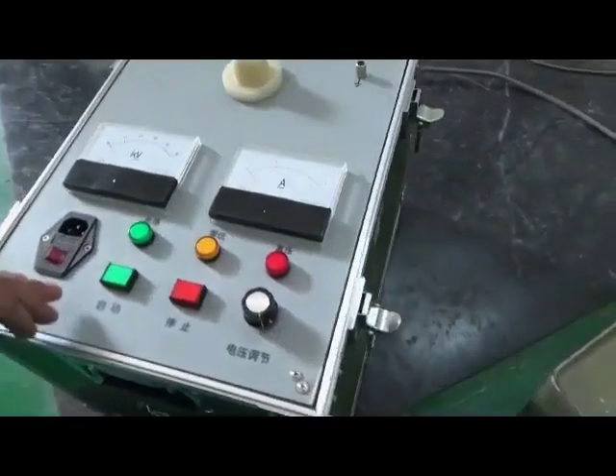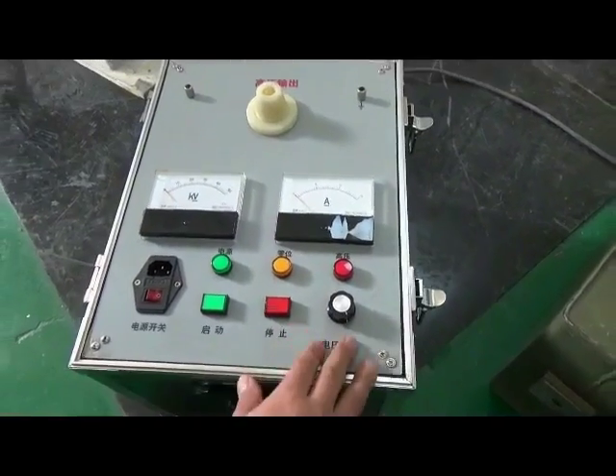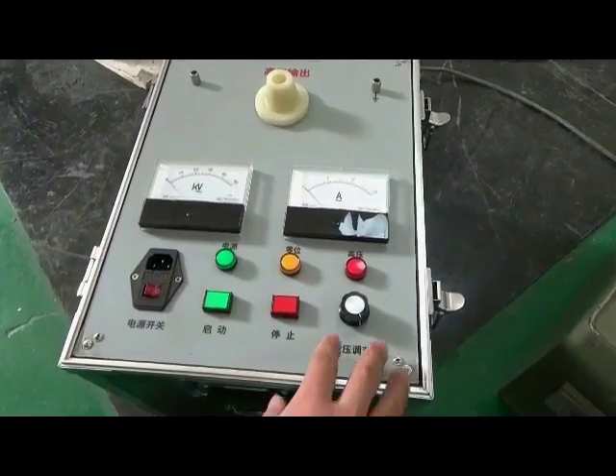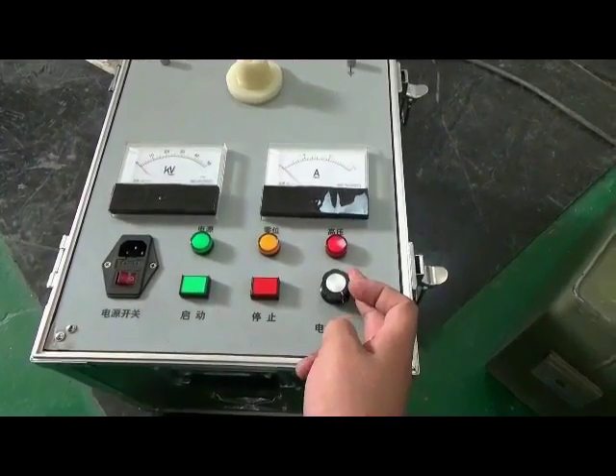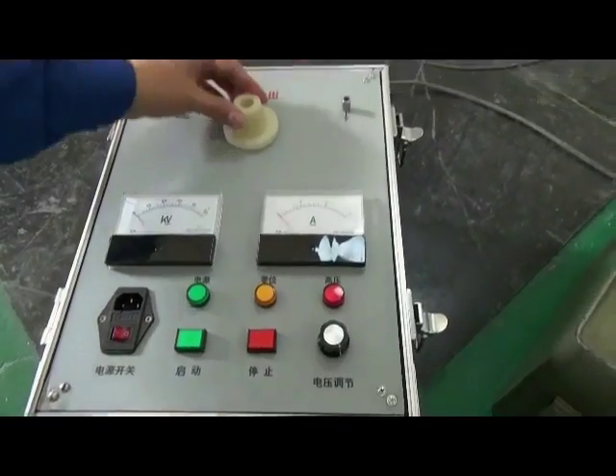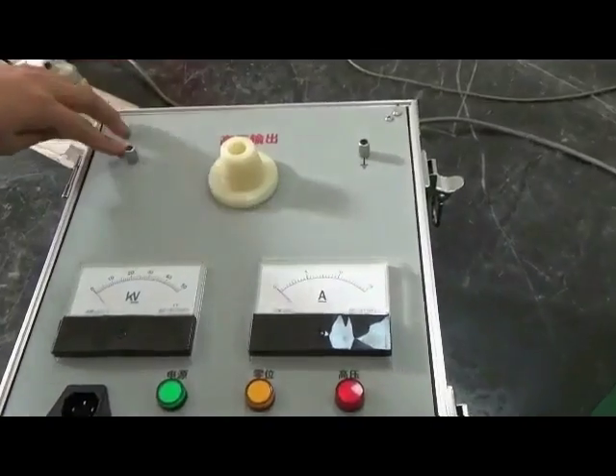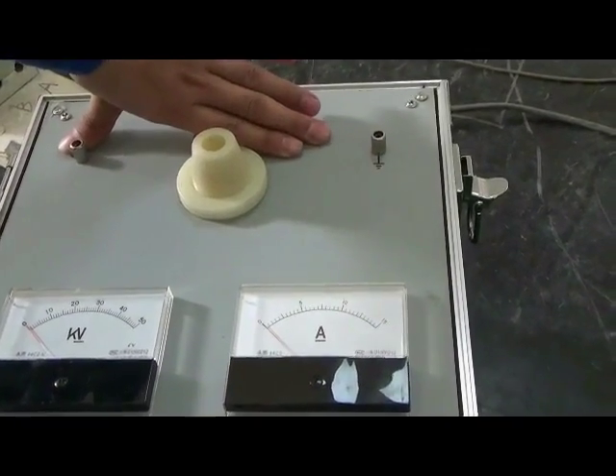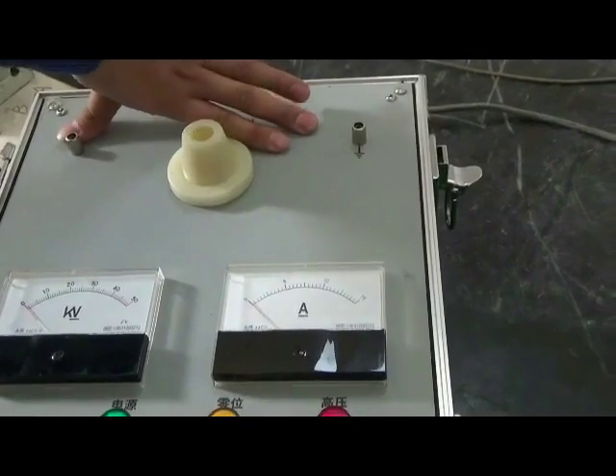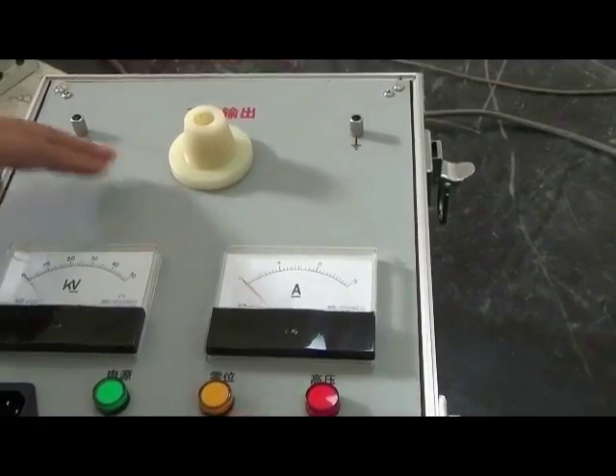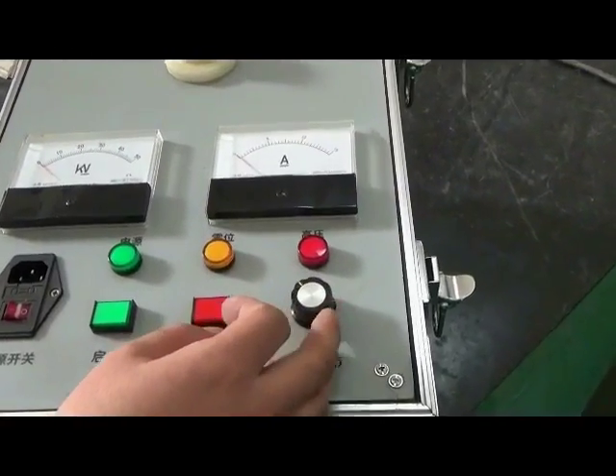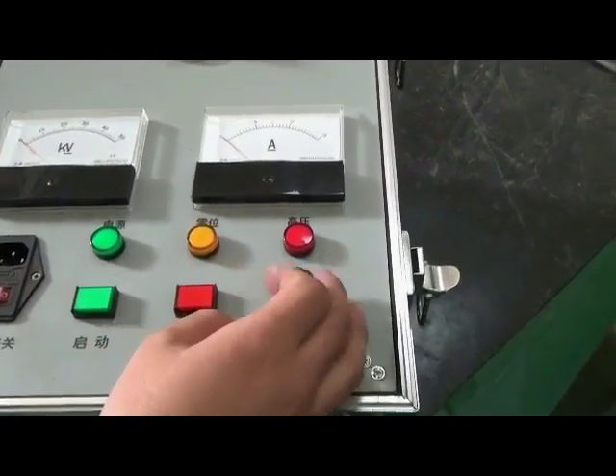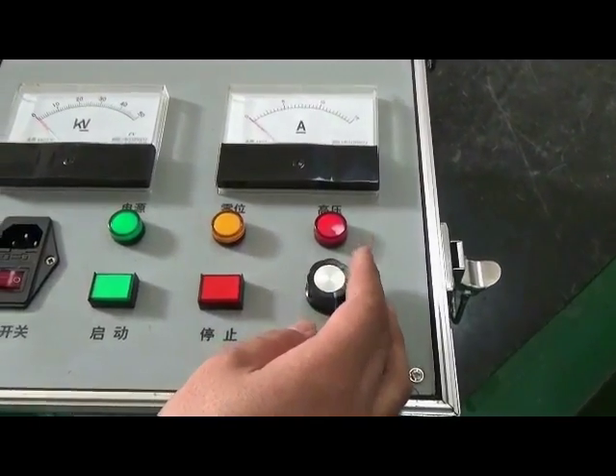High voltage power supply: the voltage must be adjusted to zero before starting up. High voltage output terminal must be kept in good contact. Make sure good grounding for both ground wires. In process of voltage adjusting, should be adjusted slowly and notice swing rate.